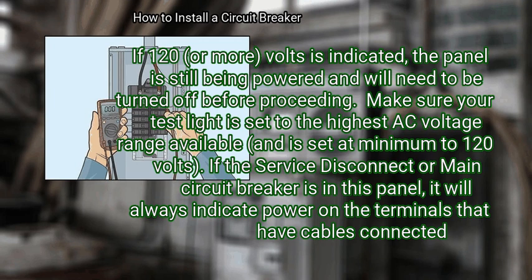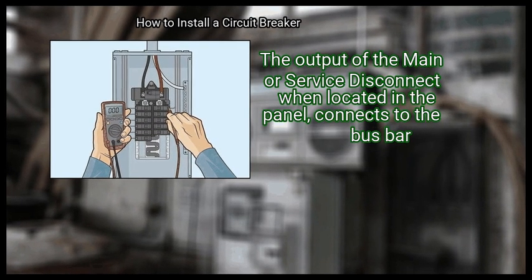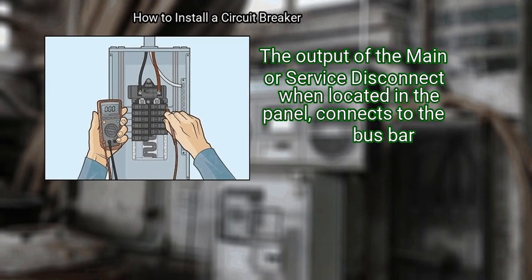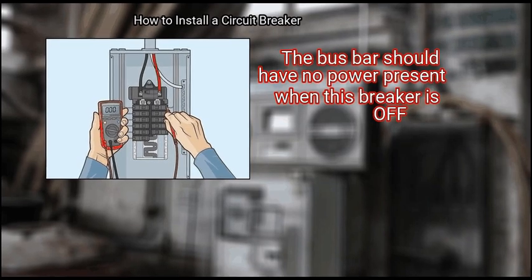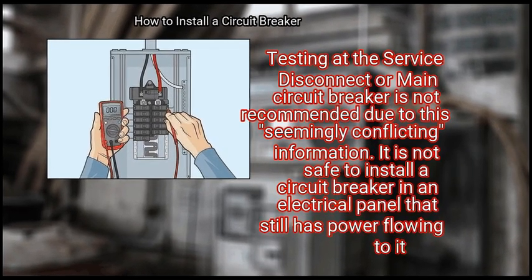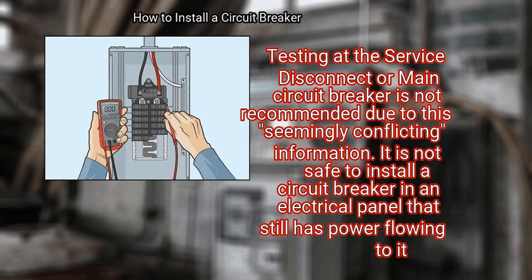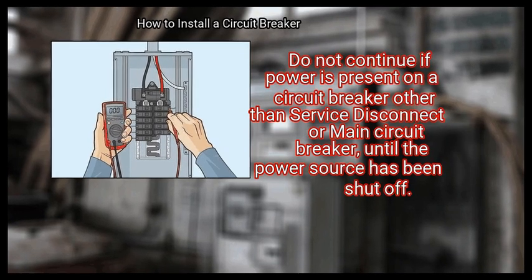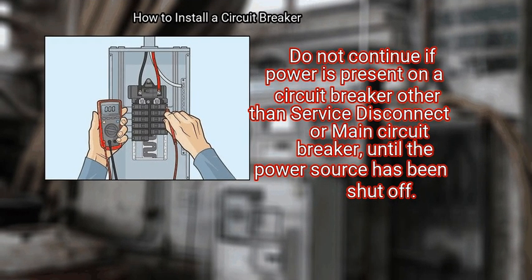Make sure your test light is set to the highest AC voltage range available, and is set at minimum to 120 volts. If the service disconnect or main circuit breaker is in this panel, it will always indicate power on the terminals that have cables connected. The output of the main or service disconnect, when located in the panel, connects to the bus bar. The bus bar should have no power present when this breaker is off. Testing at the service disconnect or main circuit breaker is not recommended due to this seemingly conflicting information. It is not safe to install a circuit breaker in an electrical panel that still has power flowing to it. Do not continue if power is present on a circuit breaker other than the service disconnect or main circuit breaker, until the power source has been shut off.